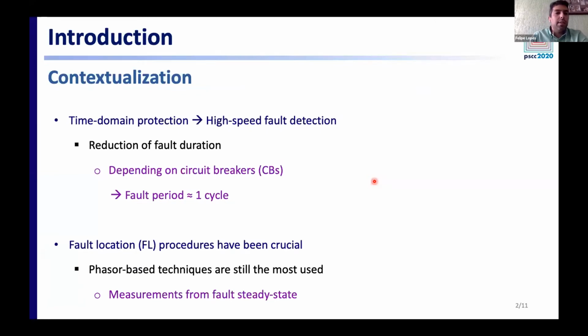We have noticed that time domain protection has gained importance in the market in the last years, and so now high-speed fault detection in the order of 4 milliseconds is a reality in our systems. And so we are expecting to verify some reduction of the fault duration, and depending on the circuit breakers, we are expecting that this fault period can reach the order of 1 power cycle only. Concomitantly, fault location procedures are still very important for utilities, and among the existing technologies, phasor-based techniques are still the most used, which in turn require measurements from the fault state.